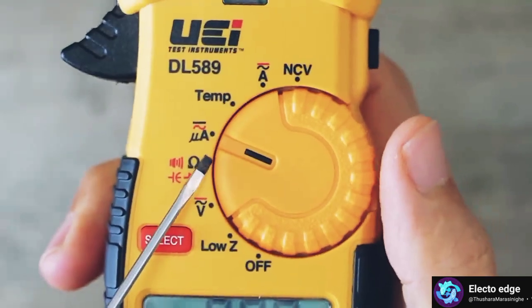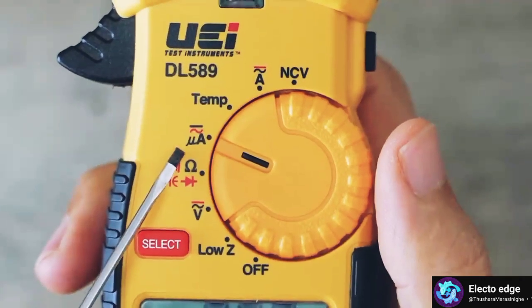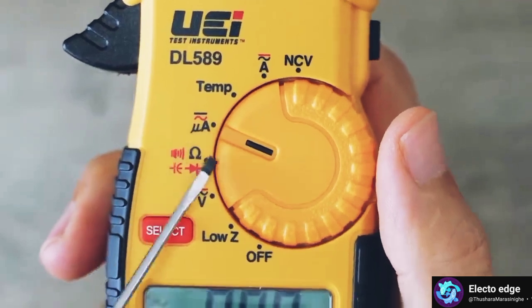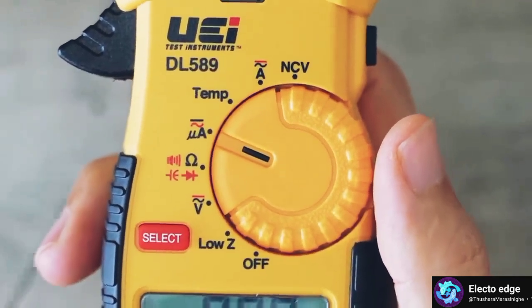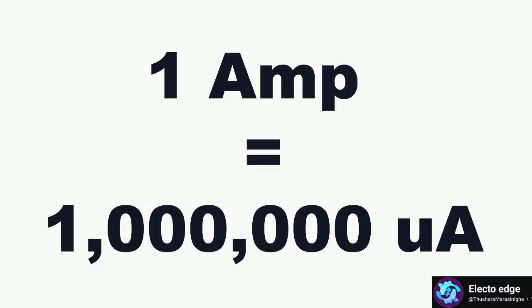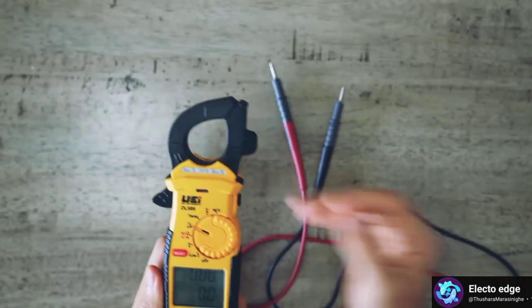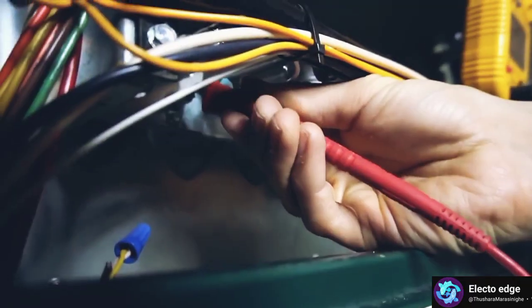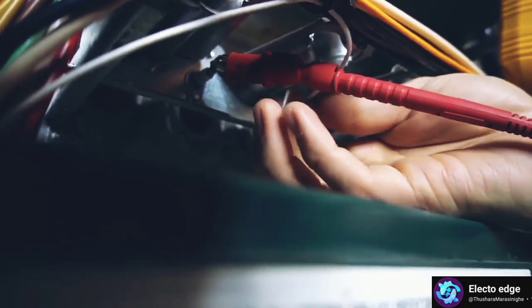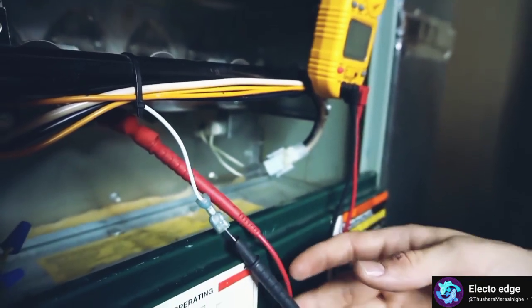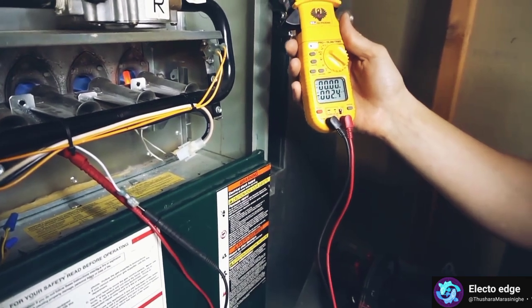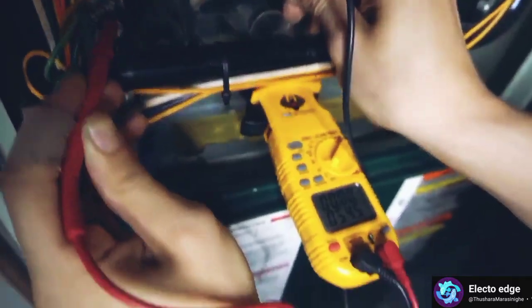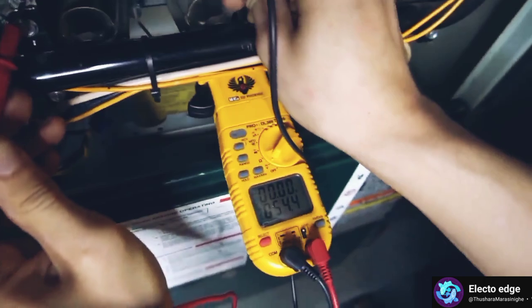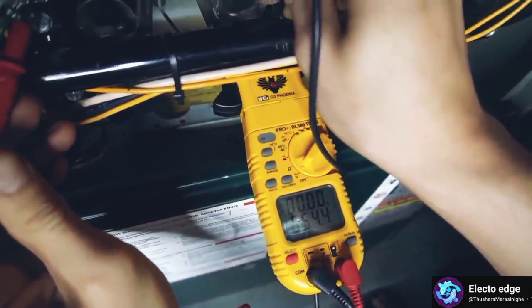So we have amps right here, and then the backwards U stands for micro. So on this setting, you can check microamps. A microamp is only 1/1,000,000th of a regular amp, so you can't use the amp clamp. The reading is way too tiny for this thing to be able to pick it up, so you have to use your meter leads, and you have to set your meter in series with whatever it is that you're checking. In heating and air conditioning, microamps are often used to test flame sensors on a furnace.